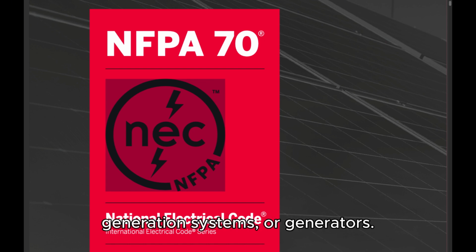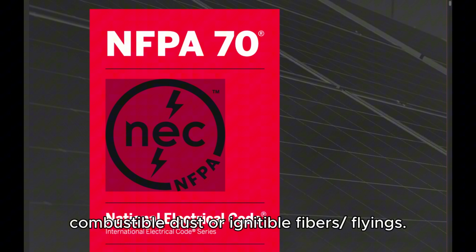Pressurized, as applied to hazardous classified locations. The process of supplying an enclosure with a protective gas with or without continuous flow at sufficient pressure to prevent the entrance of combustible dust or ignitable fibers/flyings.